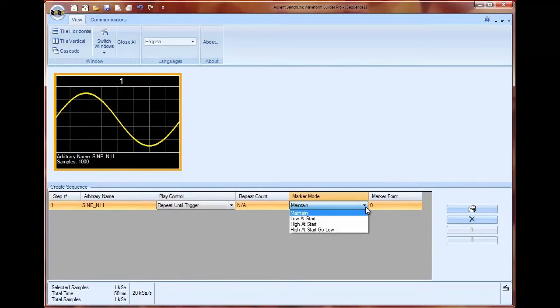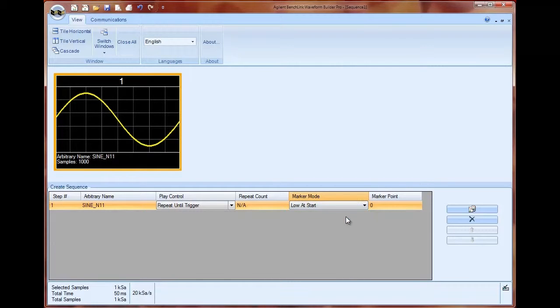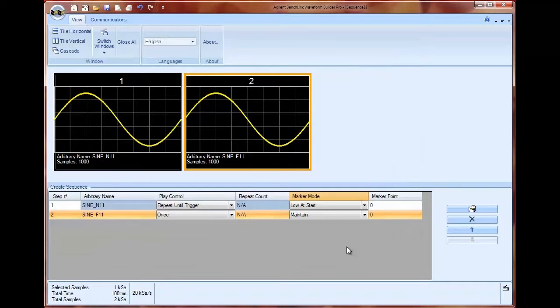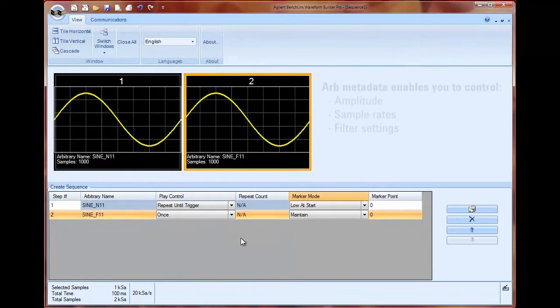And then for my marker mode I'm going to set that to be low at start and you'll see why when I load in my next waveform which is a faulty sine wave. What makes this a faulty sine wave for dropout tests is that it has a lower amplitude than my standard trigger.